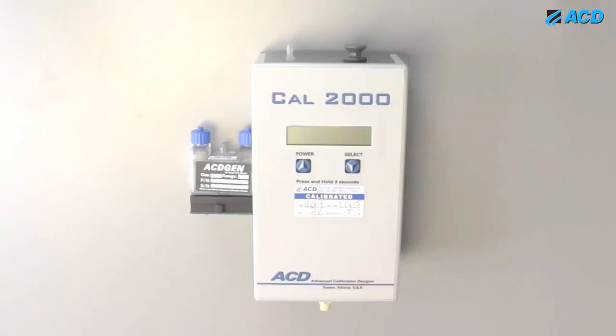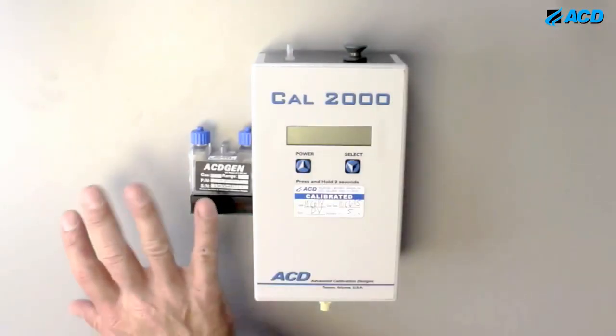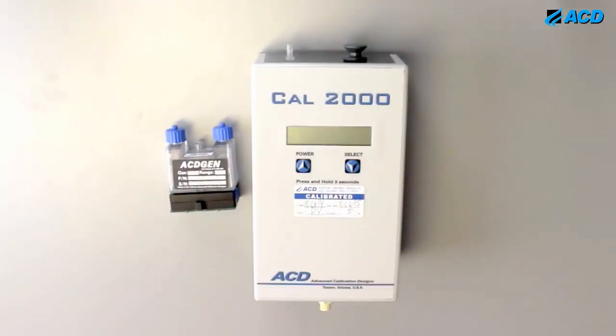Hello again, it's Kurt Ballard with Advanced Calibration Designs with an instructional video on how to operate a Cal 2000 calibration gas system. In this particular example, we've got the Cal 2000 instrument and the source we're using is for hydrogen sulfide gas.